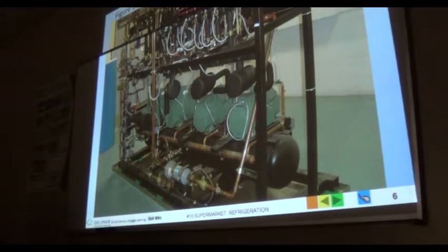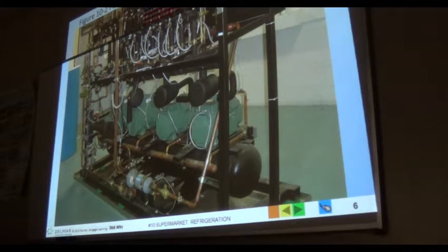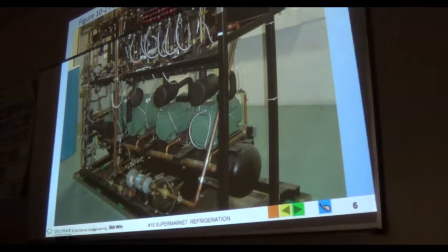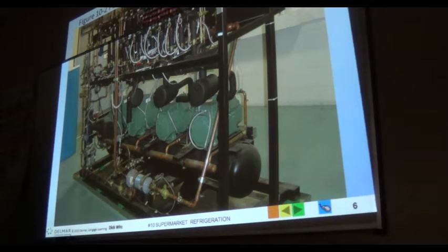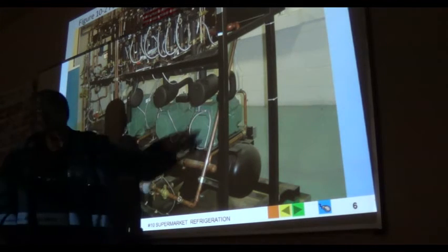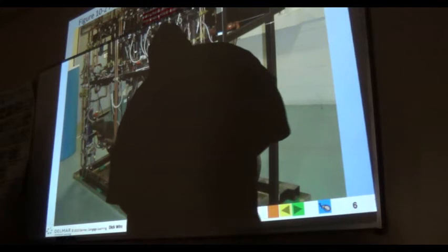The reason is because there's so much pipe and run, the vacuum cannot pull all the crap out of there. You may have used brazing flux, and some of that will still be in the copper internally, and there's a limit to what the vacuum pump can get out of that system. So what would normally happen? The high side pushes that high pressure, high velocity refrigerant, and everything will return on the suction side. So this protects the compressor from getting those solid pieces. I have opened some of these and found pieces of solid that look like marbles, very tiny, like beads, from the brazing rod.